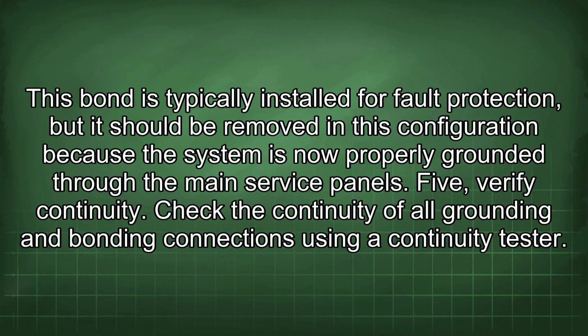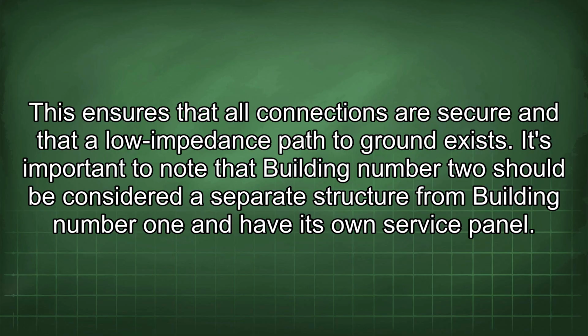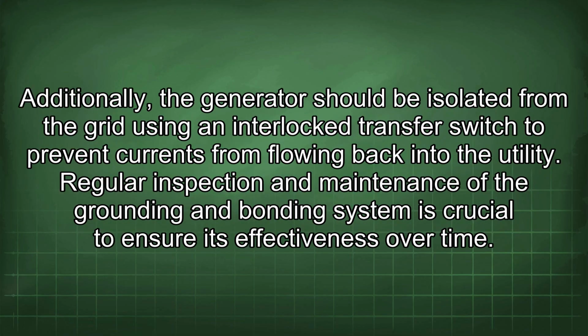5. Verify continuity. Check the continuity of all grounding and bonding connections using a continuity tester. This ensures that all connections are secure and that a low impedance path to ground exists. It's important to note that building number 2 should be considered a separate structure from building number 1 and have its own service panel. Additionally, the generator should be isolated from the grid using an interlock transfer switch to prevent currents from flowing back into the utility.